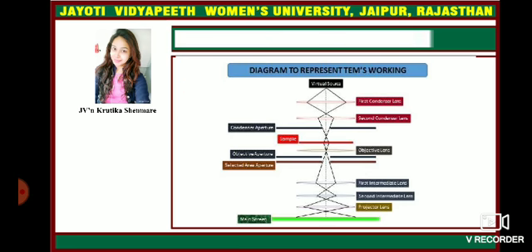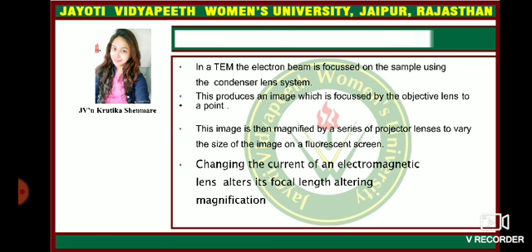This basic block diagram represents the TEM's working: there is a source of electrons, a first condenser lens, a second condenser lens, a condenser aperture, and a sample through which the electron beam is transmitted. It then passes through the objective lens into the selected area aperture, and onto the main screen where it can be recorded. The electron beam is focused on the sample using the condenser lens system, producing an image focused by the objective lens to a point, then magnified by a series of projector lenses onto the fluorescent screen. Changing the current of the electromagnetic lens alters its focal length, thereby altering magnification.